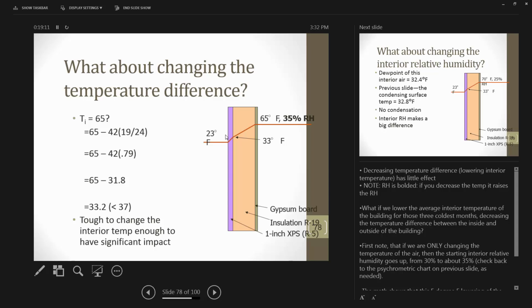By adding extra insulation on the outside of the wall, we're raising the temperature inside that wall cavity. So in certain instances, it's improving the dew point, but in a lot of situations...